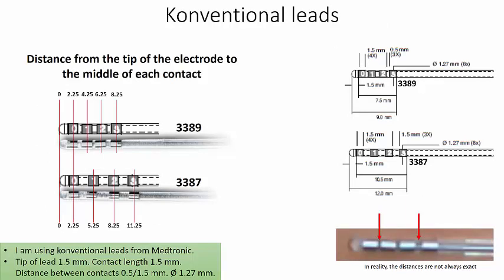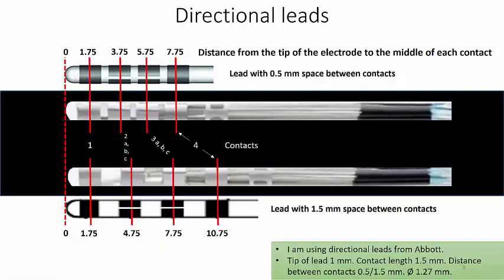When we calculate the location of the electrode, it is of course necessary to know the technical specifications of the electrodes which you are using. I am using conventional leads from Medtronic, where the tip of the lead is 1.5 mm, and the length of the contact 1.5 mm, and depending on the model, separated by 0.5 or 1.5 mm. I am also using the new directional leads from Abbott. Here the tip of the lead is only 1 mm and the contact length 1.5 mm, with the same distance as mentioned regarding the Medtronic electrode.